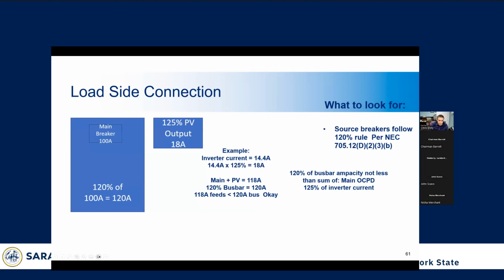All right, so here's a simple look at a common load side connection calculation that's used to determine if the panel board is large enough to accommodate the PV system. It's known as the 120% rule. So you have the main breaker, which is 100 amps, and then at this site you would probably have a 20 amp breaker for the backfeed breaker, but the max inverter current is 14.4 amps. So you'd multiply that by 125%, you get 18. So this system is fine to install with a load side connection because 18 is less than 120% of the main breaker and the bus bar rating. So that's how you do that.